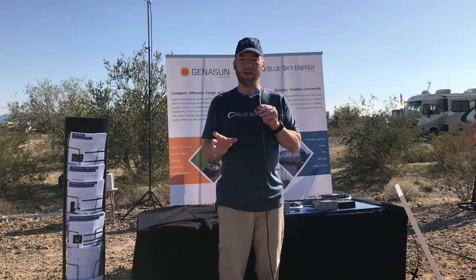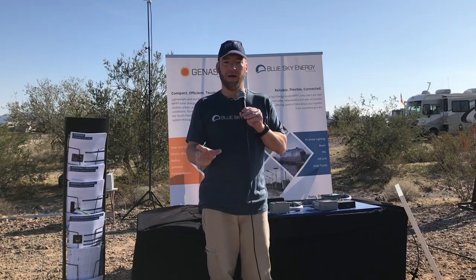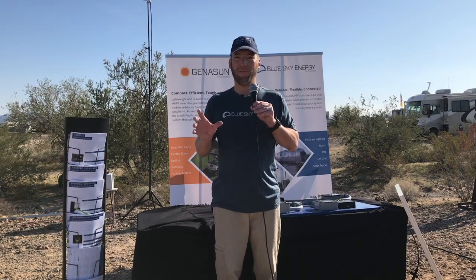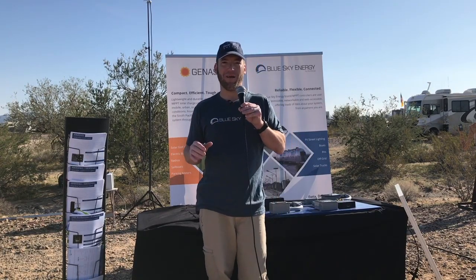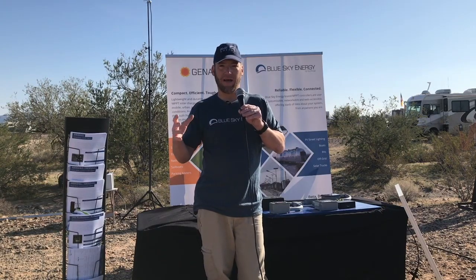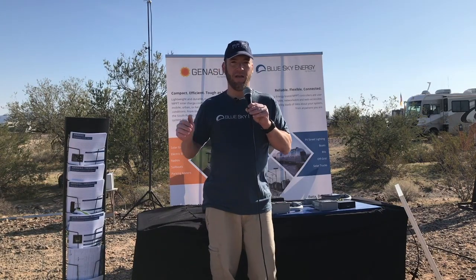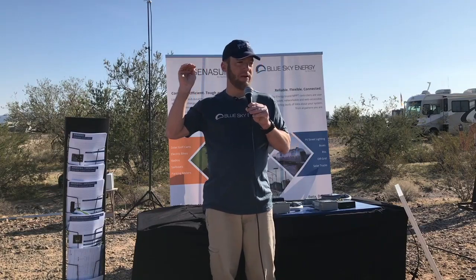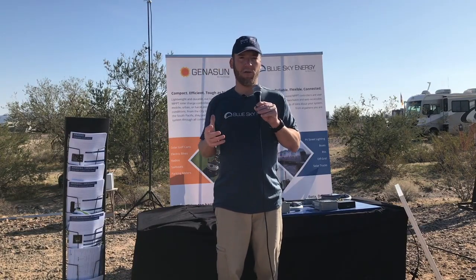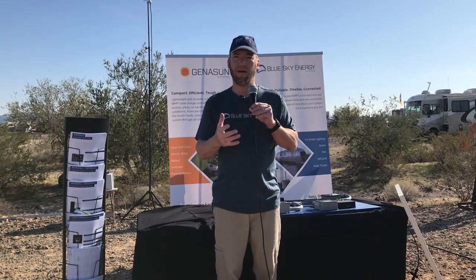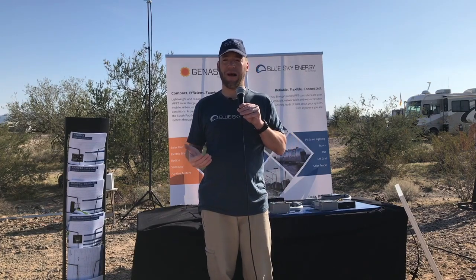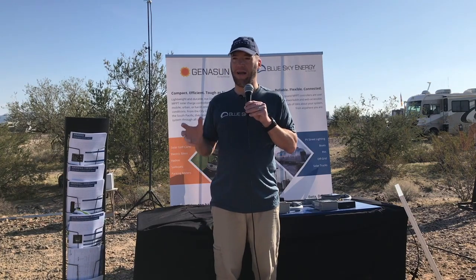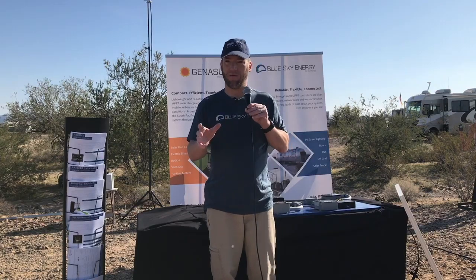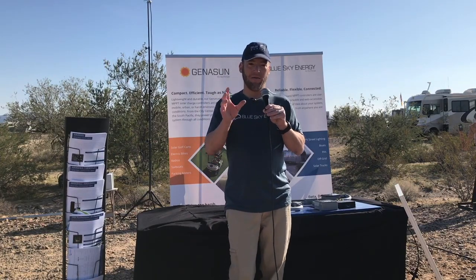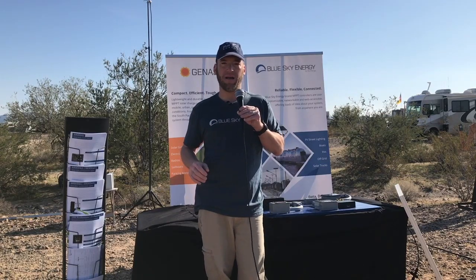Battery construction: you've got the lead plates, and then there's that secret sauce, the paste that goes around these plates. The higher and longer you stay at that absorption voltage, the more you degrade that paste, and that's what eventually causes lead acid batteries to die - that's why your lead acid battery only lasts 5 or 7 years. It's a combination of no more paste, or sulfation becoming too hard to turn back into acid.